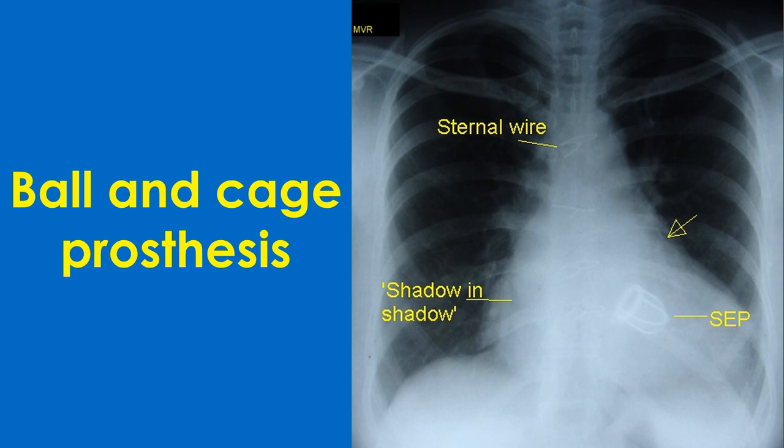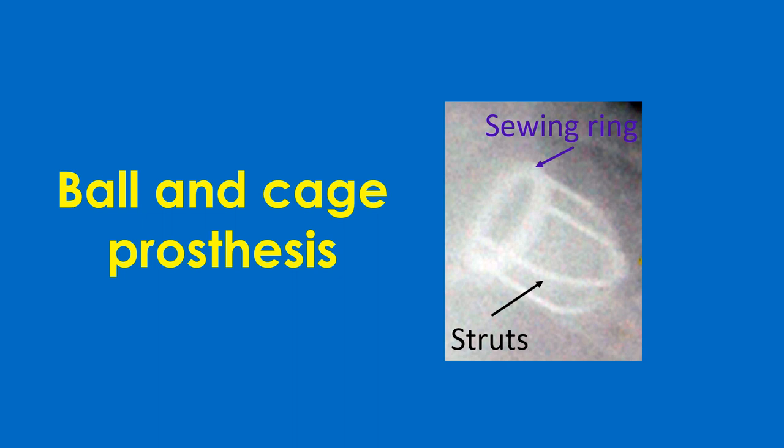The older valves were of ball-and-cage design. The prototype was the Starr-Edwards valve, which was the workhorse with valves functioning well in a person over five decades. However, due to other problems, the valve has been discontinued. The design consists of a cage with a sewing ring and struts. The mitral valve had 4 struts while the aortic had 3 struts. A ball-shaped poppet moved back and forth during the cardiac cycle to open and close the valve.